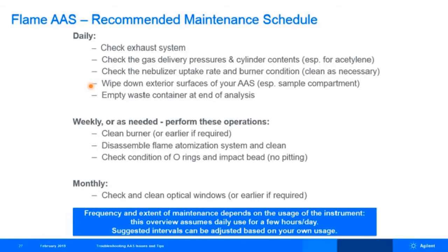Once we're finished, then of course it's recommended that we shut down the burner and wash out the sample introduction system and then empty the waste container. And it's also good practice to wipe down the exterior surfaces of your atomic absorption system, especially in the sample compartment, just to remove any acid residue that may have built up on those surfaces.